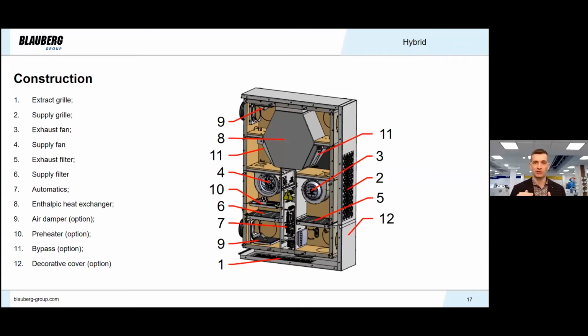heat exchanger keeps the water between the plates and it gets frozen, while the enthalpic heat exchanger transfers the water through the membrane to the exhaust air stream or to the supply air stream, depending on what is more humid. So in case the humidity of extract air is lower than 45%, which is normal for winter conditions, there would be no condensate at all, yes? But we must keep in mind that if the humidity of extract air is from 45 to 70%, the drain pan would be needed to collect some condensate.